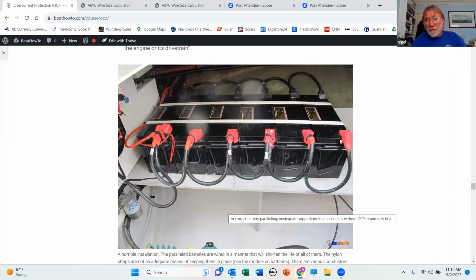When you parallel batteries, and most of us have, if we've got moderately sized boats, more than one battery paralleled together in our battery banks. If you parallel batteries in this fashion, and you take the conductors to the loads off of one end of the bank, when the boat is either charging or discharging, this battery is going to do more work than this battery. As it does more work, it will heat up. When it heats up, it gets more reactive and it does even more work. We get into a vicious circle where this battery is working really hard and this one's doing very little work. And with 6 of them like this, we are guaranteed to destroy all the batteries fairly quickly, within a year or so.